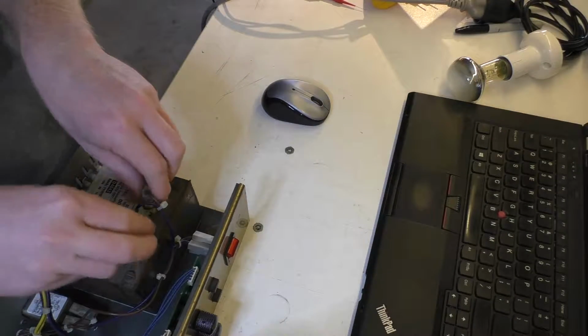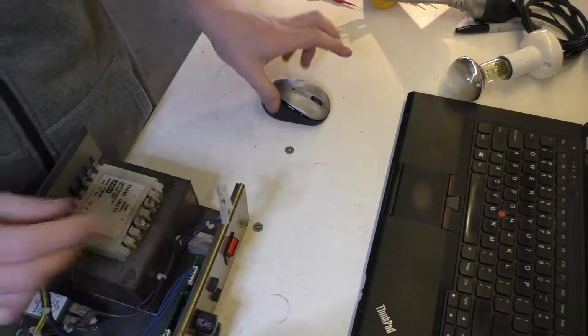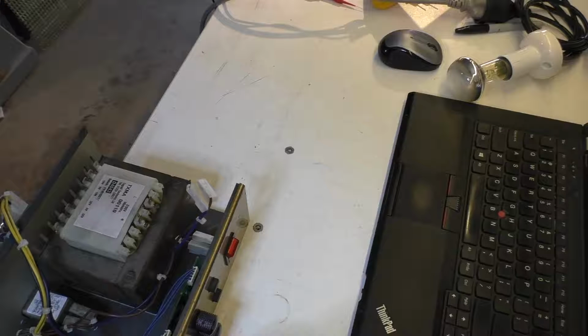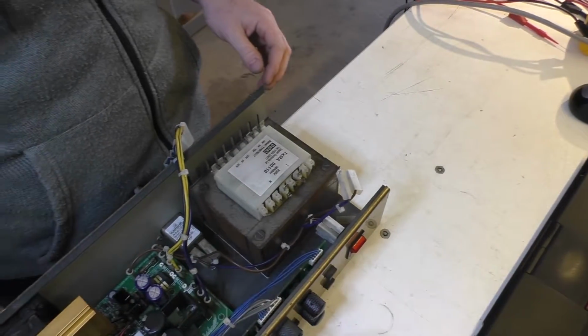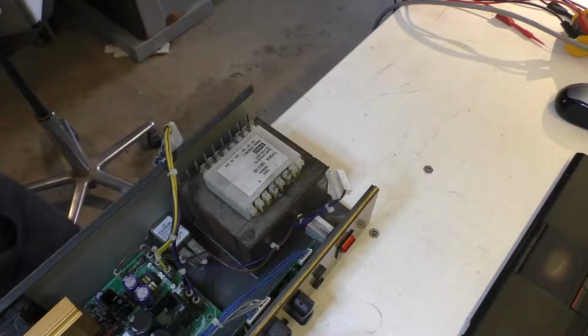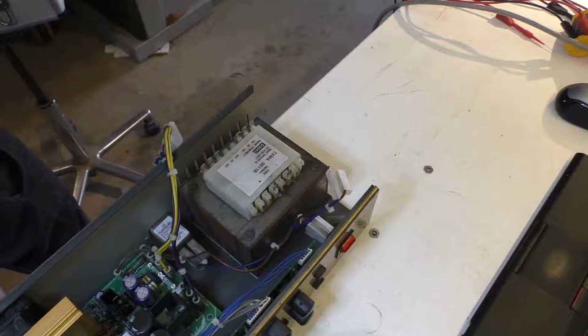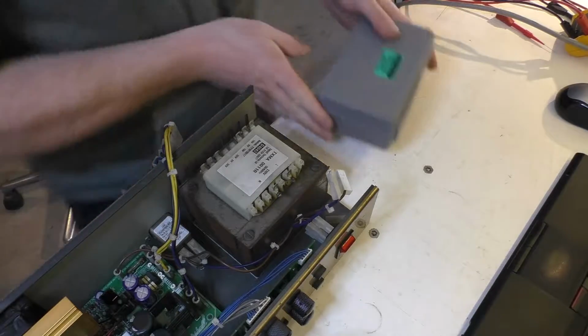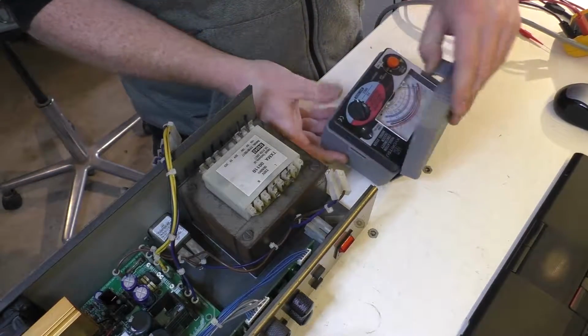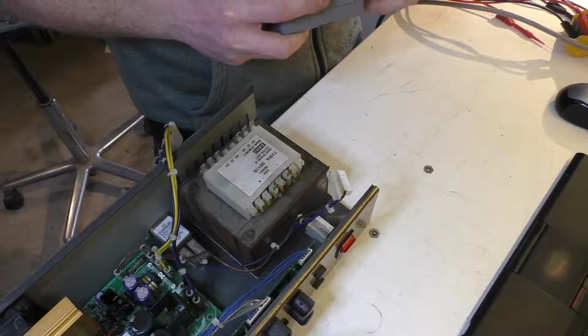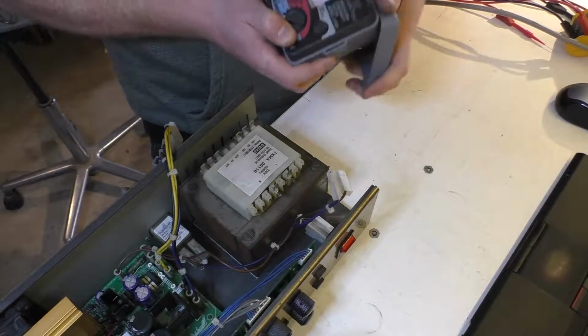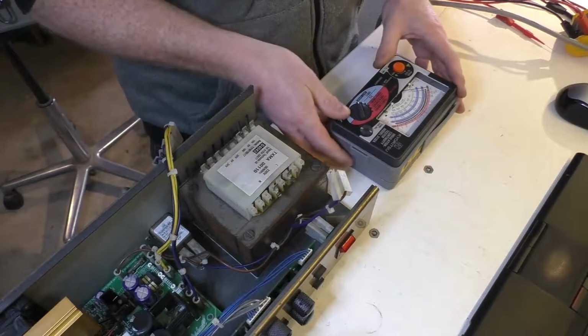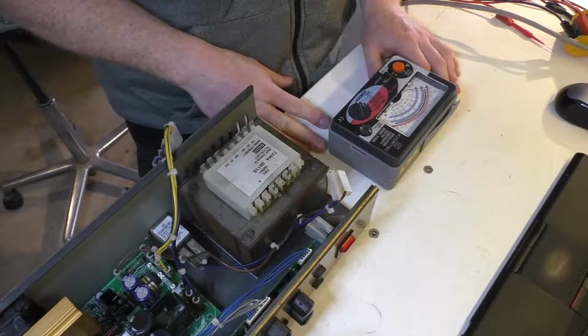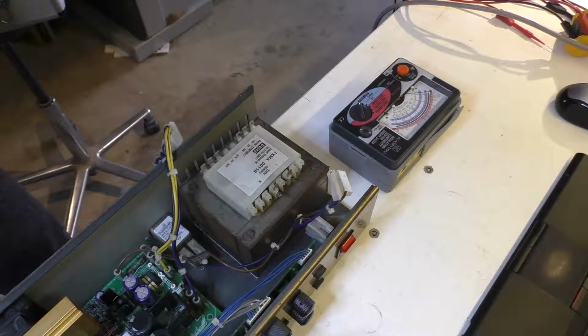Alright, well I might hipot test that, so I get out the insulation tester, see what's going on. Man, I should have tested that before I cleaned the thing up. Alright, so I get this scary bastard out. No, it's not, there's scarier ones, but this goes up to 1,000 volts. There's some that go up to like 10,000. Probably should have got a 2 or 5,000 volt one, but if something's drastically wrong, this will show it.